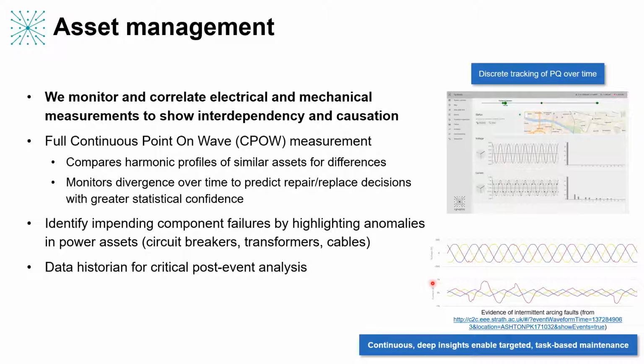So continuous point-on-wave sets out to address that. There's been work done by NASPI in America, by National Grid and others in the UK, to see how we could move from synchrophasor-based systems to continuous point-on-wave, in which case you're not calculating the phasor and transmitting that, you're literally transmitting all of the measurement data sample by sample back to a central location. That sounds like a gigantic IT challenge, and it is, because there are a lot of challenges in terms of bandwidth and data security, but that's where we're able to help. Because our sensor networks are all passive, we don't need that infrastructure to be there. Because we timestamp everything at a central location, you don't need to distribute network time to each of those measurement locations, nor do you need the alternative, which is GPS access at each of those locations to get a good timestamp.